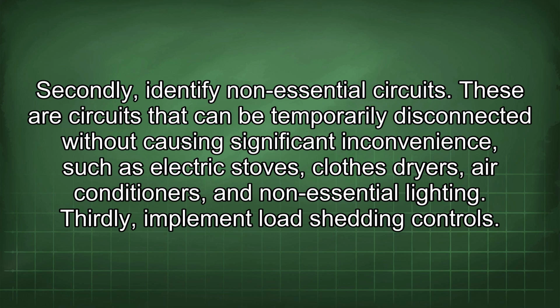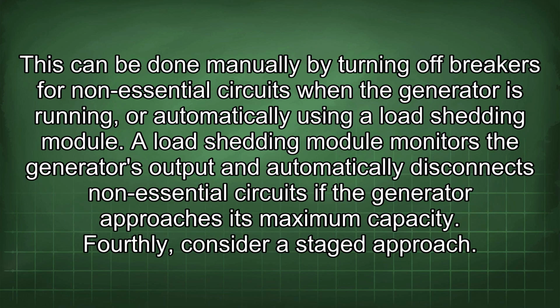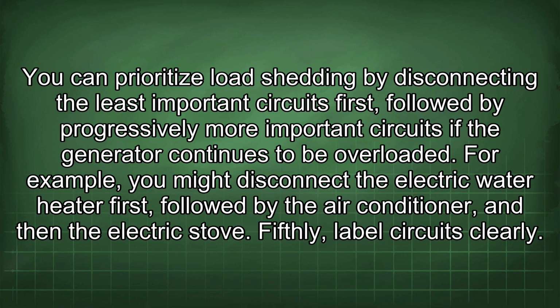Thirdly, implement load shedding controls. This can be done manually by turning off breakers for non-essential circuits when the generator is running, or automatically using a load shedding module. A load shedding module monitors the generator's output and automatically disconnects non-essential circuits if the generator approaches its maximum capacity. Fourthly, consider a staged approach. You can prioritize load shedding by disconnecting the least important circuits first, followed by progressively more important circuits if the generator continues to be overloaded. For example, you might disconnect the electric water heater first, followed by the air conditioner, and then the electric stove.